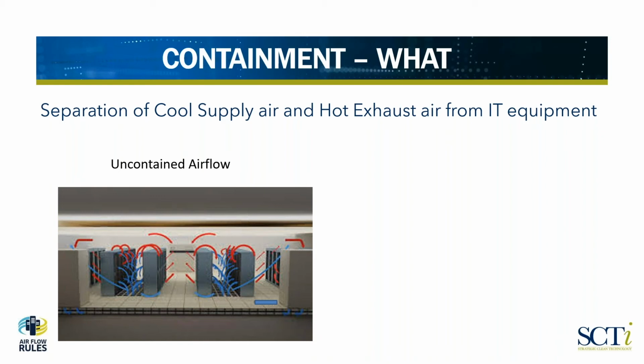The first one being, of course, that if the hot air is coming back around to the front of the racks, you're getting a higher airflow temperature, higher air inlet temperature than what could be desirable for your IT equipment, which eventually could lead to high temp alarms on the IT equipment, or could actually lead to potentially failure of the IT equipment.